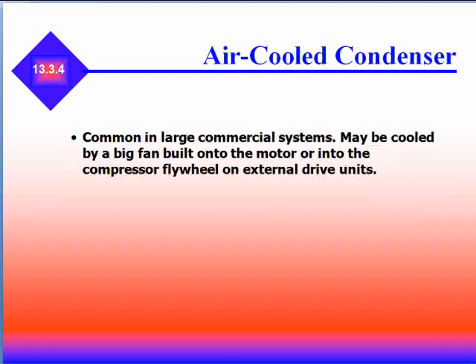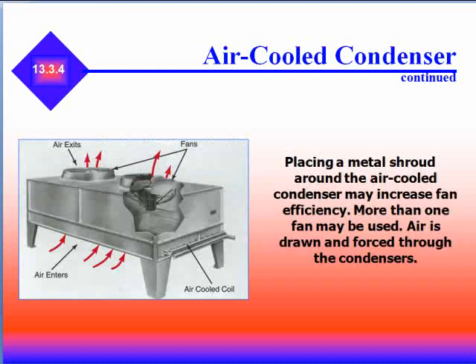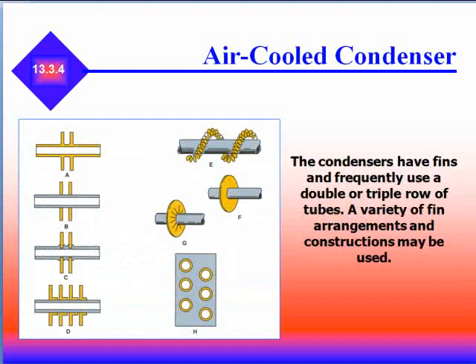Air-cooled condensers are common in large commercial systems. They may be cooled by a large fan built onto the motor or into the compressor flywheel on external drive units. Placing a metal shroud around the air-cooled condenser may increase fan efficiency, and more than one fan is used. Air is drawn and forced through the condensers, which have fins and frequently use double or triple rows of tubes. A variety of fin arrangements and construction may be used.